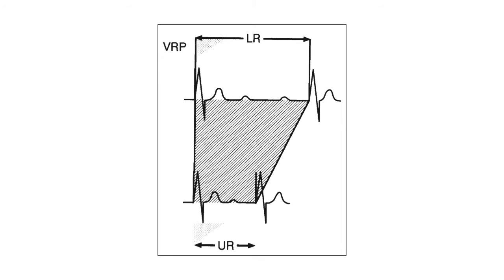It includes both the basic VV and AA interval and a refractory period from the paced or the sensed events, as we have said before. The only difference lies in the variability of the VV or AA intervals. So, depending on the sensor incorporated and the patient's exertion level, the basic interval is shorter than the programmed lower rate limit, and this shortening requires programming another timing of the pacemaker, which is the upper rate limit, to define the absolute shortest cycle length allowable.